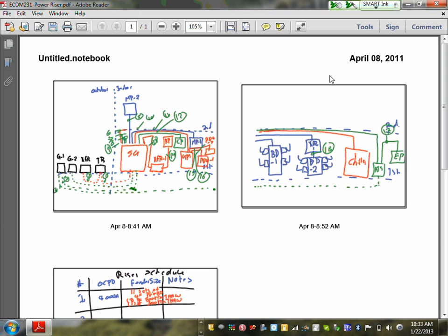So here's where it gets interesting. Generator 1 comes up to speed. It's feeding this transfer switch from the generator side, and it transfers, boom, 10 seconds. Then a little bit later, now we're on Gen 1, Gen 2 here. Power's back up from the normal side, but it's still on generator. Well, the transfer switch is going to switch to normal power, even though it's generator. But you just have to make sure this gets up and running in 10 seconds. So you have to have a second breaker, and a separate ATS for your life safety.